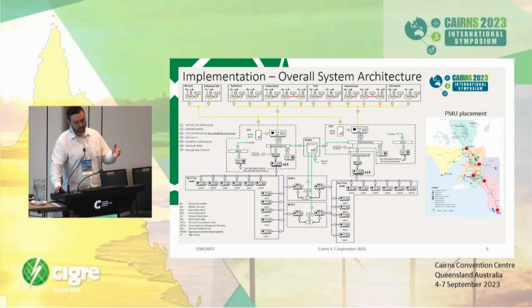So if the control scheme was to operate, it then triggers via GOOSE. There's a protection relay that decodes the GOOSE and then hardwires the trip signals to tripping devices, and then they're sent downstream via a multiplex C37.94 network.